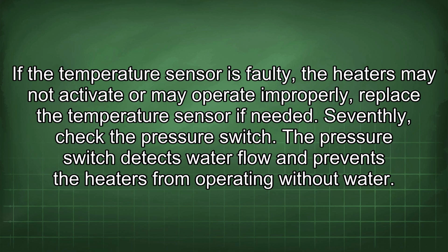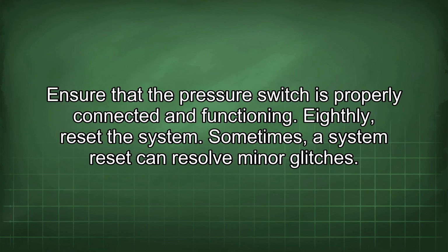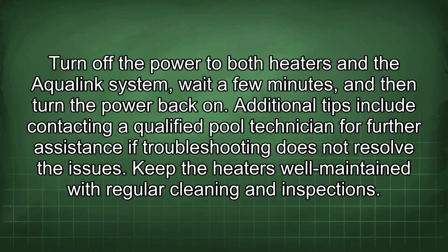Seventhly, check the pressure switch. The pressure switch detects water flow and prevents the heaters from operating without water. Ensure that the pressure switch is properly connected and functioning. Eighthly, reset the system. Sometimes a system reset can resolve minor glitches. Turn off the power to both heaters and the Aqualink system, wait a few minutes, and then turn the power back on. Additional tips include contacting a qualified pool technician for further assistance if troubleshooting does not resolve the issues.